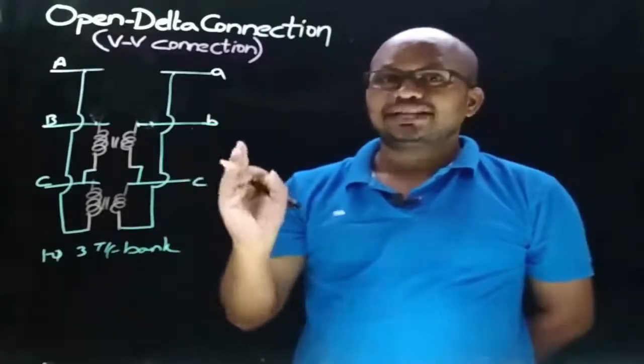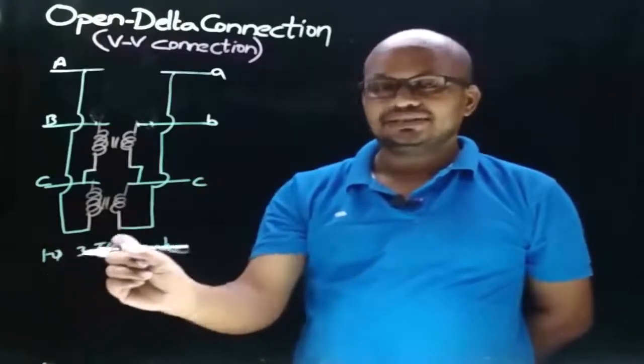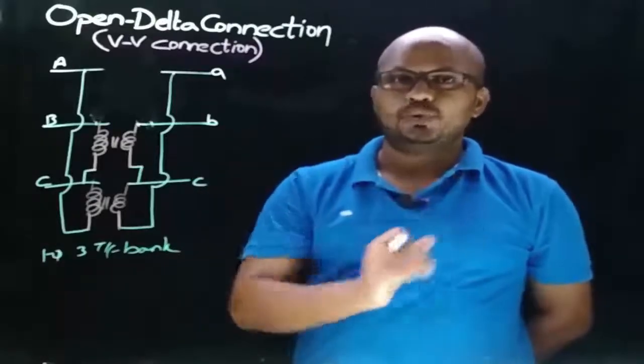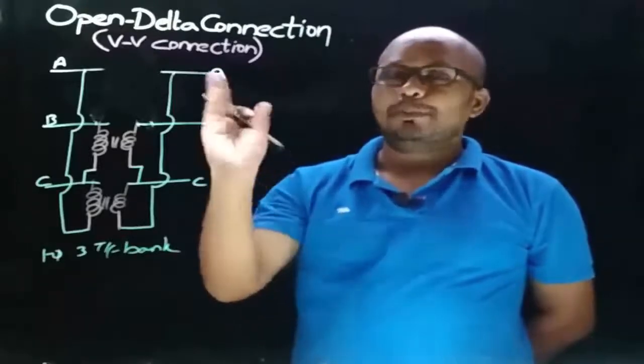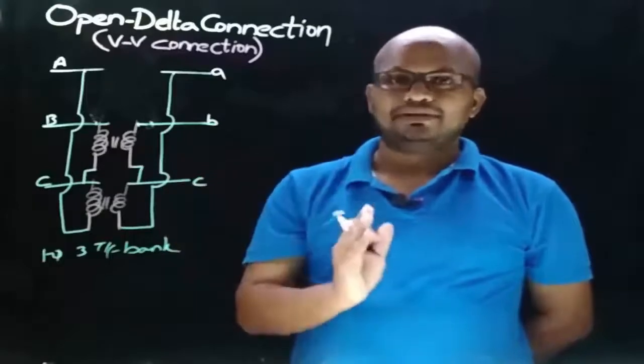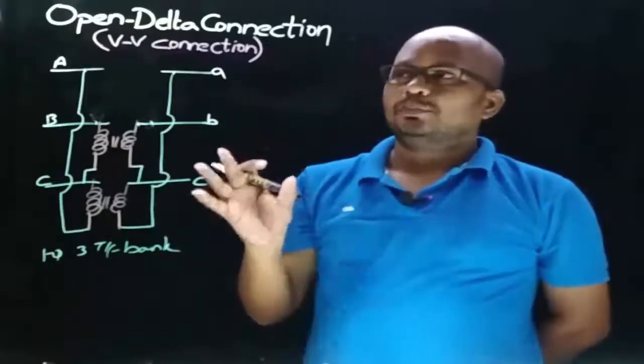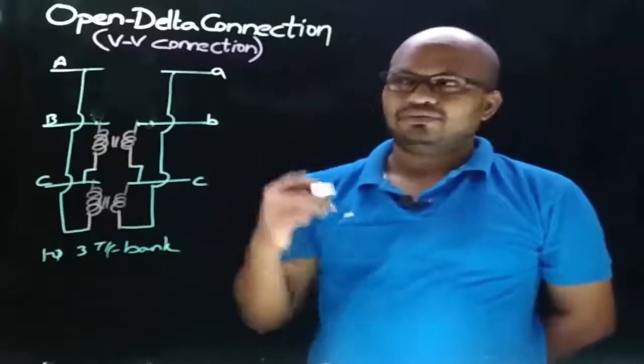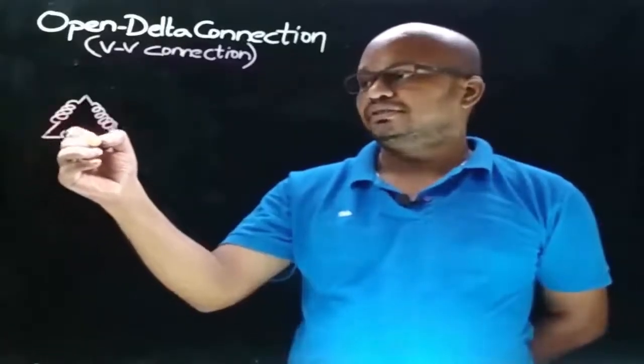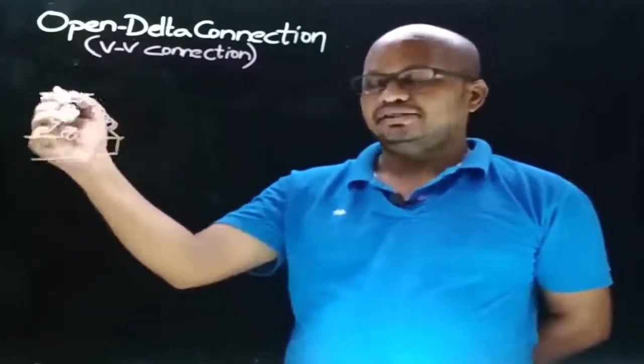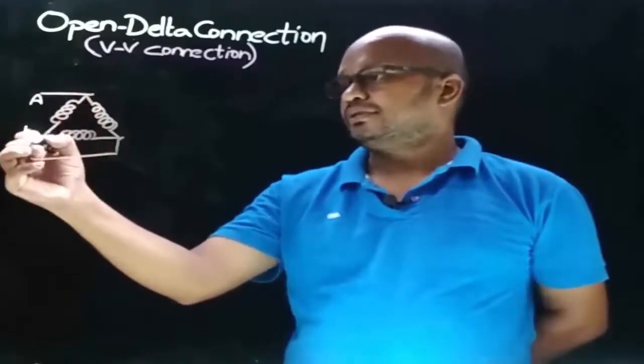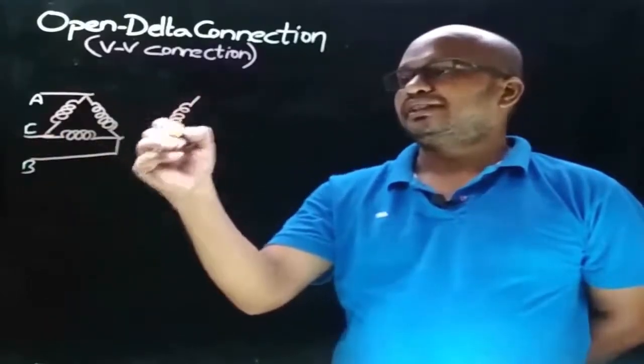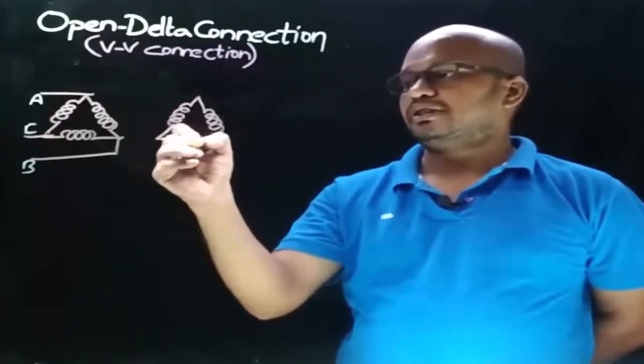This resultant winding connection is called open delta connection. Keep this point in mind: when one of the transformers in a delta-delta connected single-phase three-transformer bank gets failed, we generally think there will be a power interruption to the load. But with open delta connection, we can maintain the continuity of supply to the load, but with reduced capacity. Let's redraw the delta-delta connection in a simple manner and observe the open delta connection.